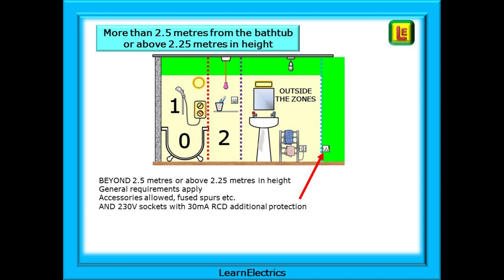Beyond 2.5 meters from the edge of the bathtub, or more than 2.25 meters in height, we are into the green zone on this drawing. Many bathrooms will just exceed 2.25 meters in height — great for mounting ceiling pull switches. But most bathrooms will not have floor spaces greater than 2.5 meters from the bath. In the green space, the general requirements apply to any equipment or wiring. Accessories are allowed — fused spurs, etc. And 230 volt sockets are permitted, but they must have 30 milliamp RCD protection.